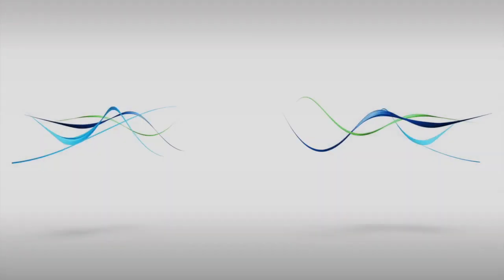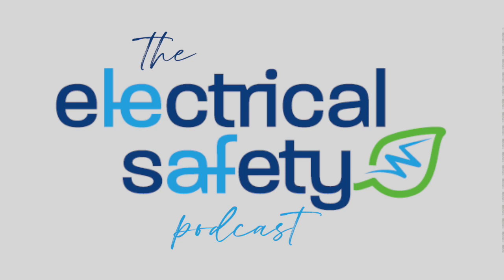But if you get a large bird, such as a hawk or something on a crossarm on a pole, if he's sitting on that once, but if he spreads his wings out and he makes contact with the other phase or to the ground on that, then now we have a fault, right? So equipotential zone is a key aspect of temporary protective grounding.